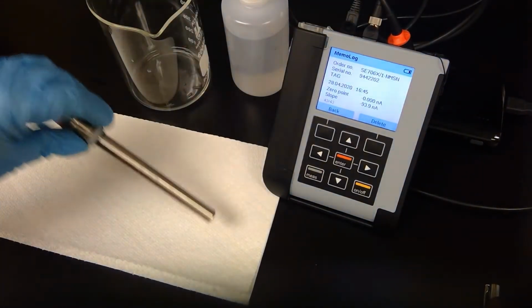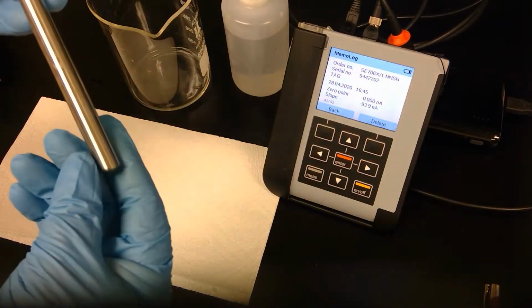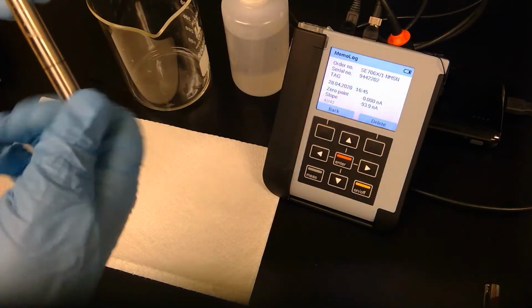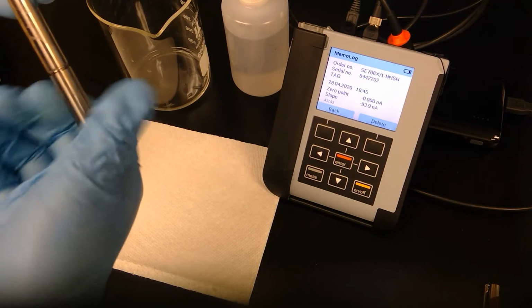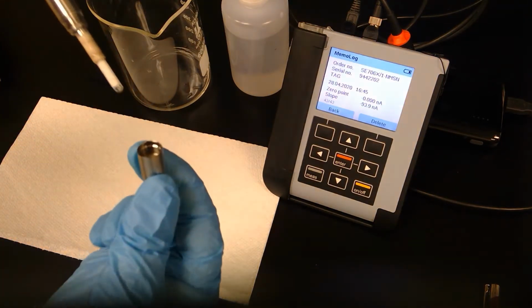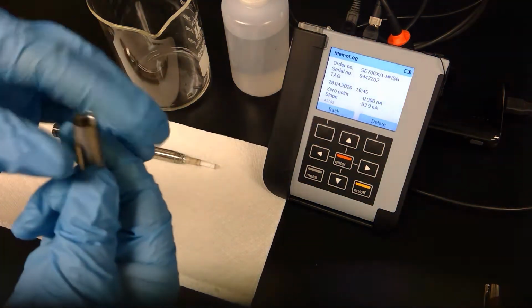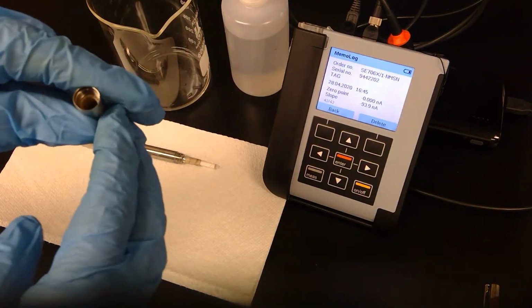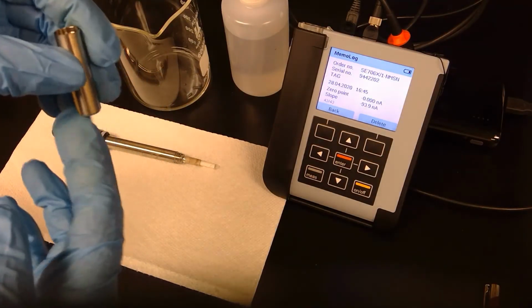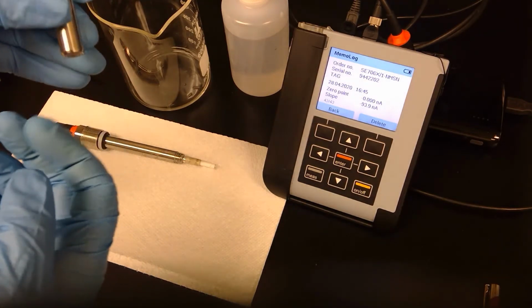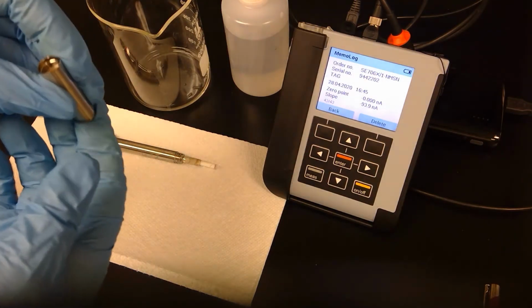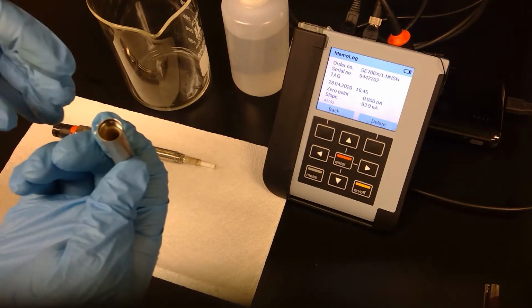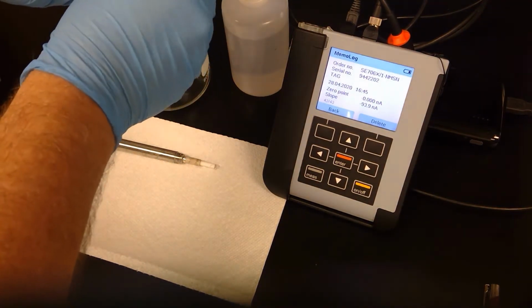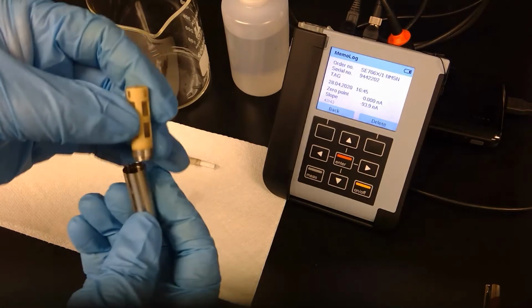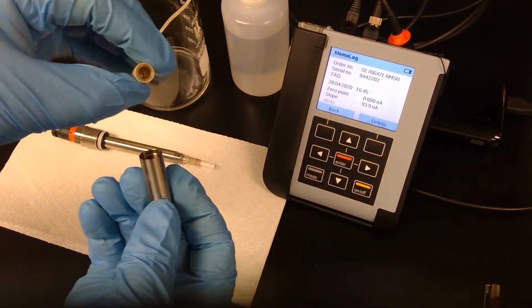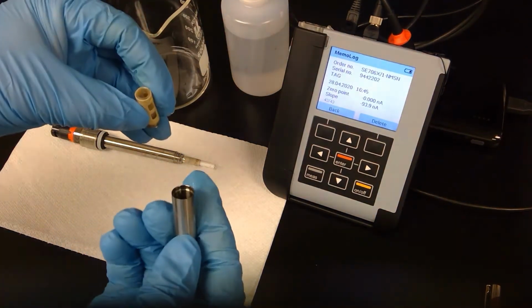Now, what you need to do in this case is remove the sleeve off the sensor. And all you do is just like that. We'll put the electrode down. What you have here is an external sleeve, and then you've got the membrane that's down inside. The way to get the membrane out is just push on it here, and that pops it out. And there you go. That just came right out of the sleeve. This is the old membrane. There was a little bit of electrolyte in there.